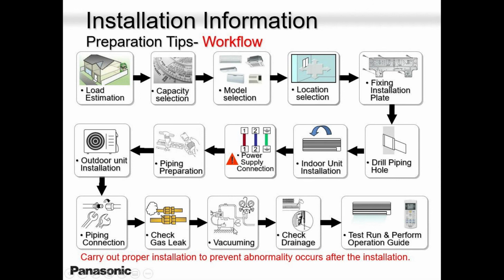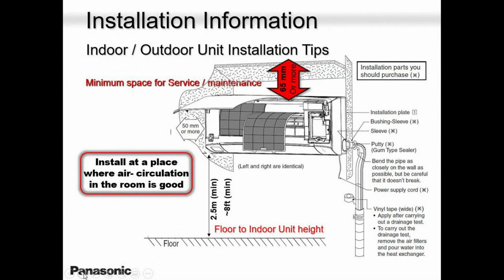Then you have the power supply hole. Always remember, when you're making a hole, drill it at a slant. I know when you're making holes for your furnaces or water heaters, you go the other way, up, because it's condensing. So with your split unit, you've got to give it a slope for your drain, for your condensate drain. Don't go straight out. Always give it a slant. Give it some gradient, okay, guys? Piping connection. Make sure you do a good flare. Check for leaks. Pressurize the system. Don't over pressurize.